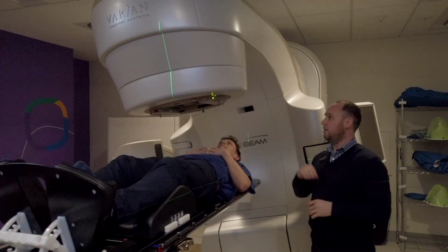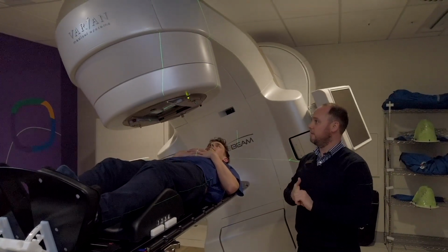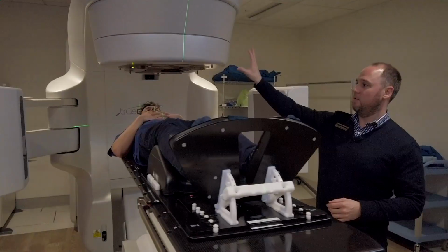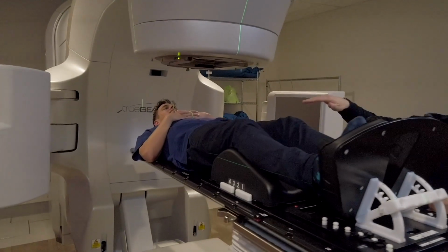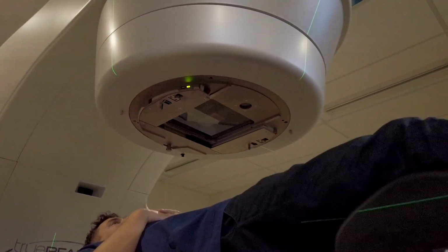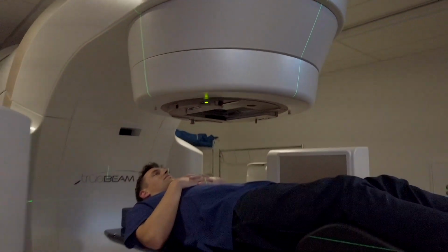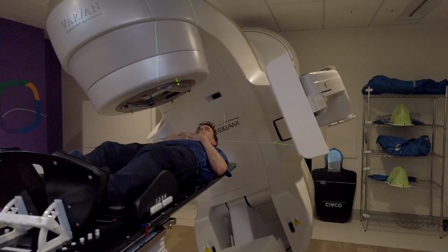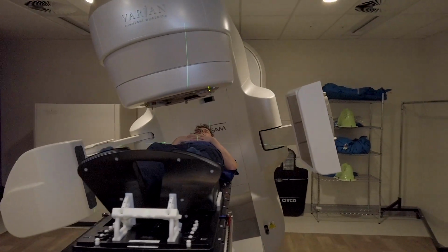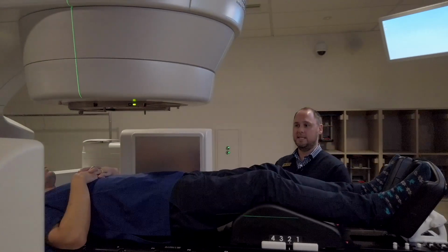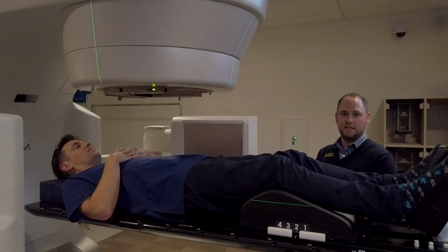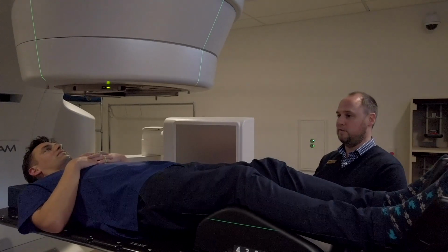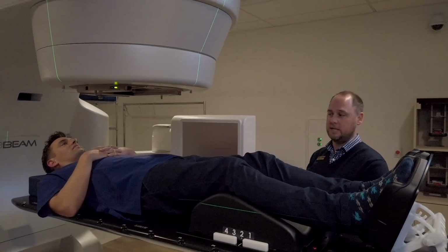So the treatment machine moves around the patient to deliver the treatment. On the machine, as well as the treatment delivery head, we also have a kilovoltage X-ray unit which is mounted to the treatment machine gantry, so we can take X-ray images of the patient's internal anatomy to verify the correct location of our treatment before we deliver the treatment. Modern machines can also take a CT scan, which we can overlay with the CT scan that we took at the original planning simulation session to verify the internal anatomy that we're treating as well.